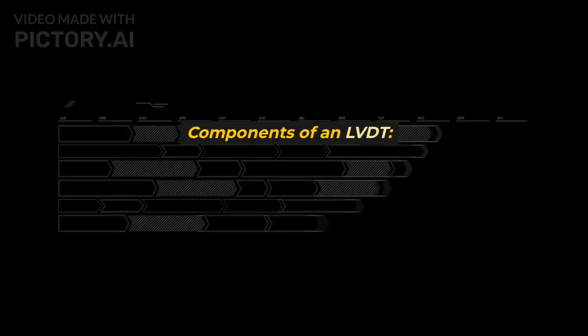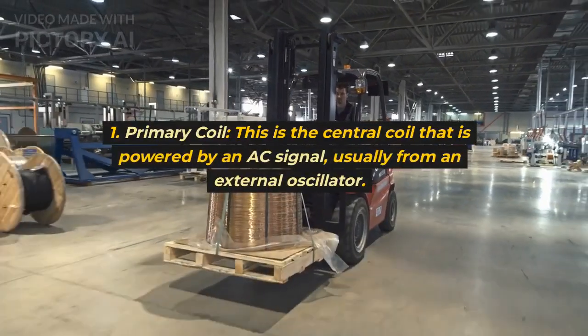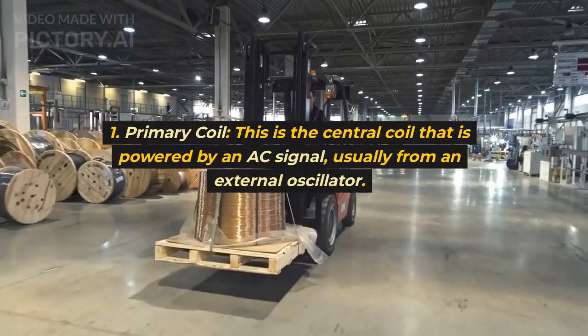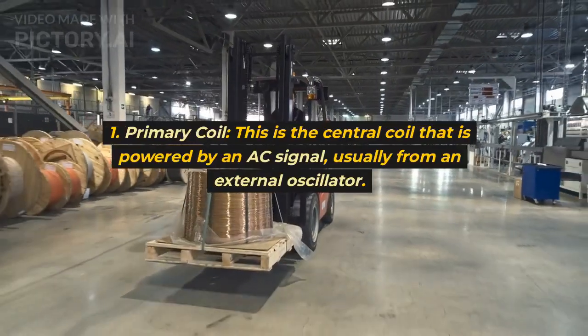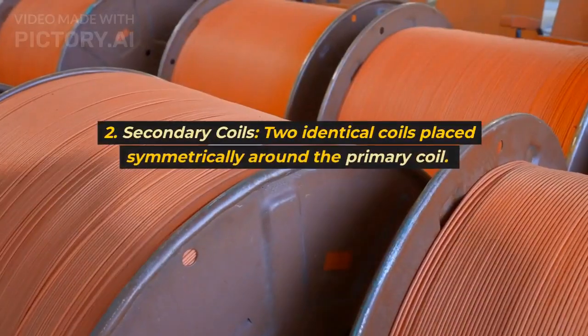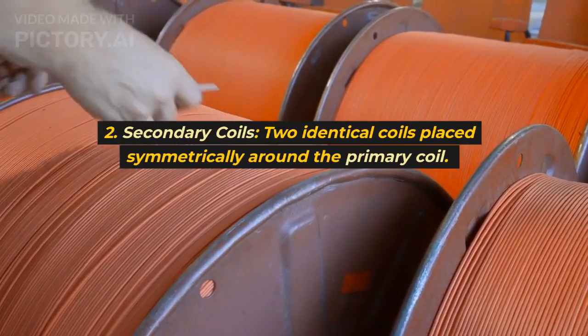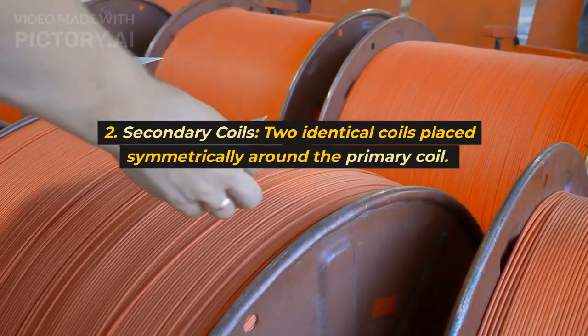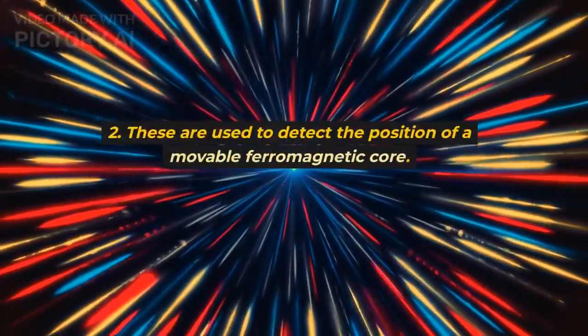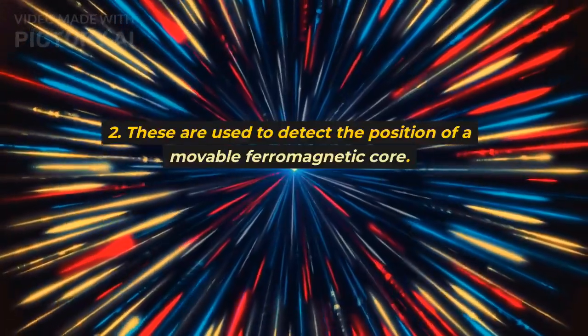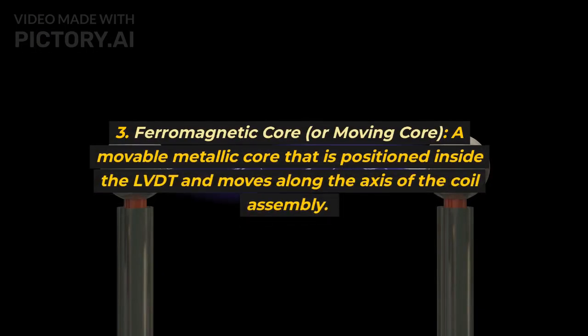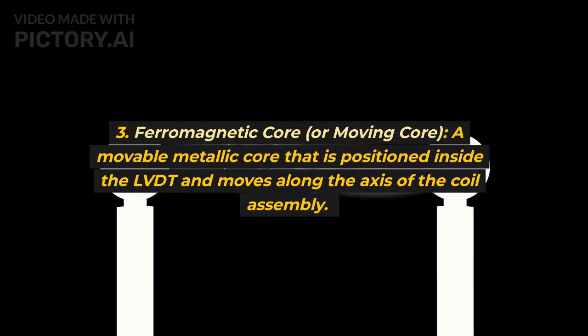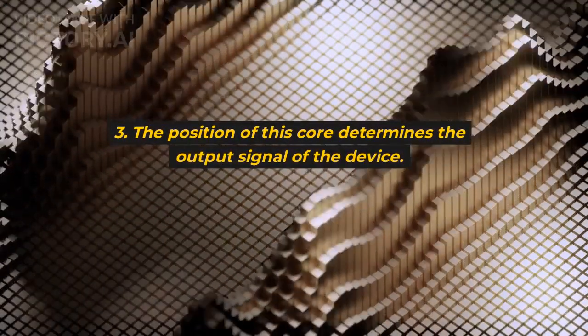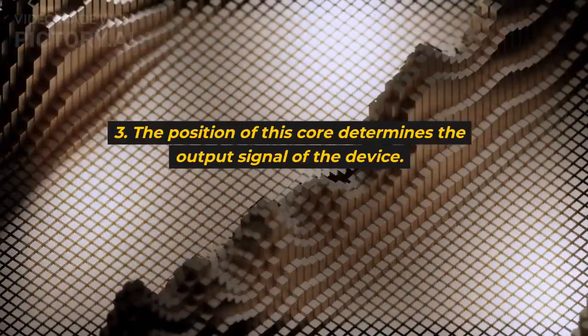Components of an LVDT. 1. Primary coil. This is the central coil that is powered by an AC signal, usually from an external oscillator. 2. Secondary coils. Two identical coils placed symmetrically around the primary coil. These are used to detect the position of a movable ferromagnetic core. 3. Ferromagnetic core, or moving core, a movable metallic core that is positioned inside the LVDT and moves along the axis of the coil assembly. The position of this core determines the output signal of the device.